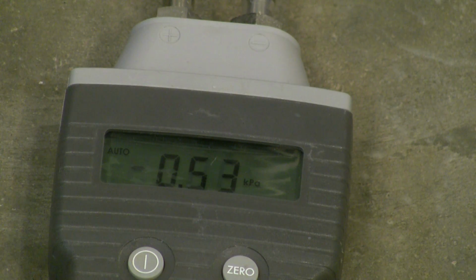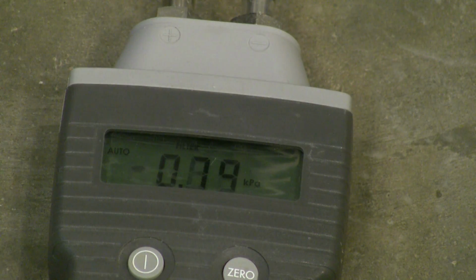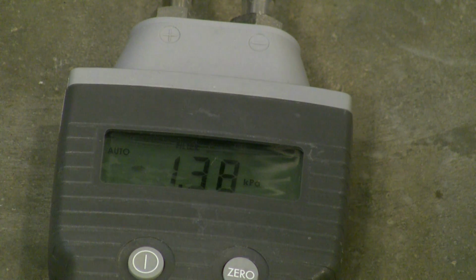Okay. I've once again opened the bottom pipe so that we're getting flow through this bottom pipe, and later on I'll let you know what the diameters of pipes are so that you can calculate the velocity that goes along with each of these different pipes that we're using. So I close it briefly, make sure that it is zeroed. I'm going to set it into filter mode to smooth it out a little bit. Okay, it's relatively zeroed. Turn the flow back on, and we can get the data here.